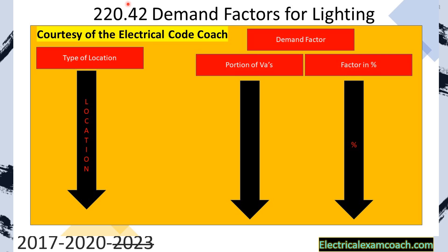We're also allowed to use it for the entire three VAs per square foot plus the 4,500 that we tacked on for the two small appliance and one laundry. Using this table, we start on the left-hand side and find our location. The first one we find is dwelling units. Then we're going to find hospitals, hotels and motels, warehouses, and really important down here at the bottom, it says all others.